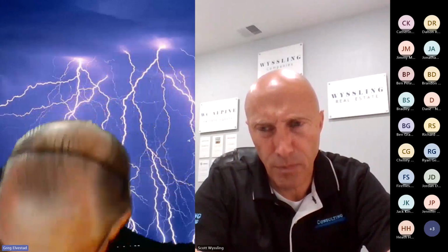The other one is the state of Connecticut has a participation, I hope it's Connecticut. Anyway, one of the northeastern states has a participation program where you set up a second meter set for interconnection, again, ahead of the utility meter. We're not talking about that today. Just want that to be something on your radar in case you see that. Don't get freaked out too badly. And also, the opposite side of that disconnect, on the customer side of that disconnect, we want to identify that as a load side.